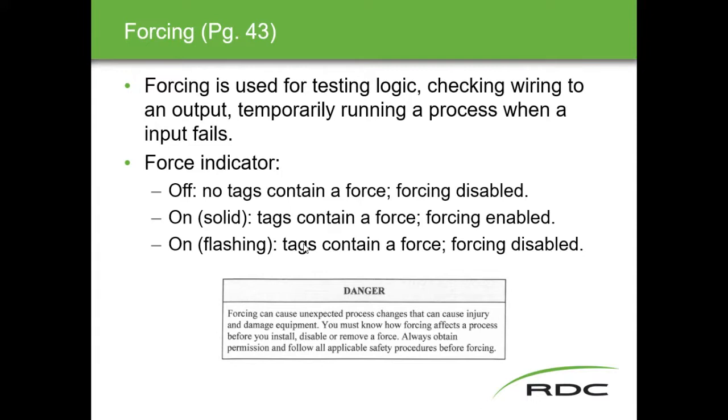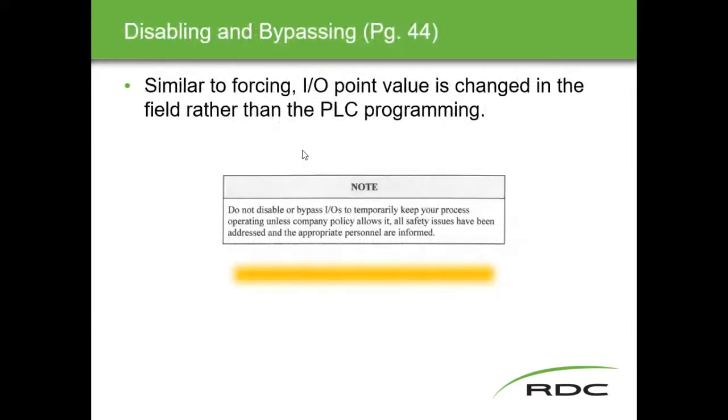But it's a very dangerous tool in a running plant. Most of you won't know this, but I've been guilty a couple of times of flooding the three-phase separator that's downstairs in the lab. I'll talk about it when we're down in the lab, but we have a little workstation for the three-phase separator that's kind of hiding behind the bench by the distillation column, and you can't really see what's going on at the separator. Anyway, long story short, I forced a couple of level outputs on the three-phase separator because it wasn't working properly and I wasn't paying attention, and I overflowed it because I had the level alarms forced off. So you've got to be careful with forces.